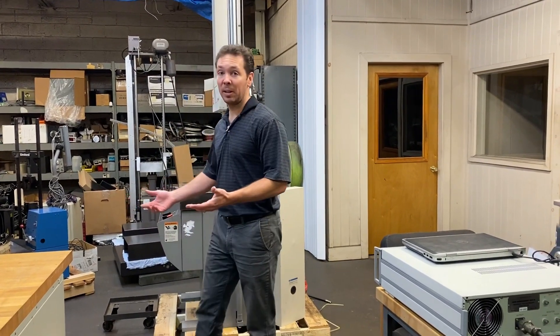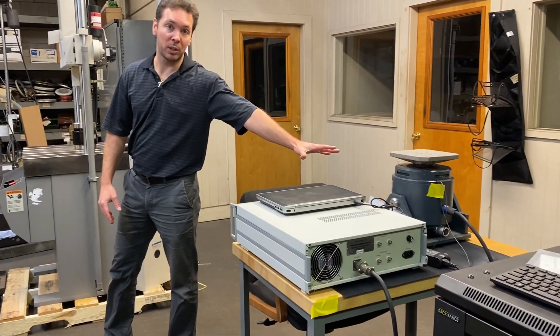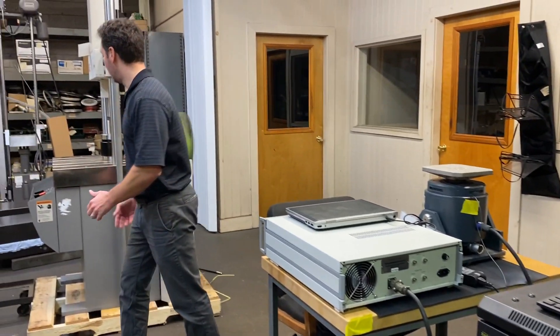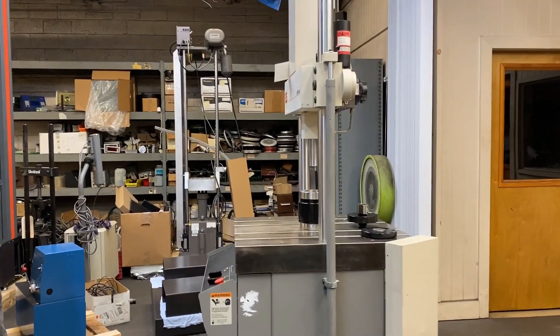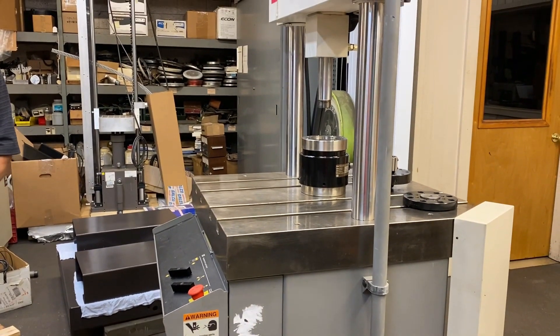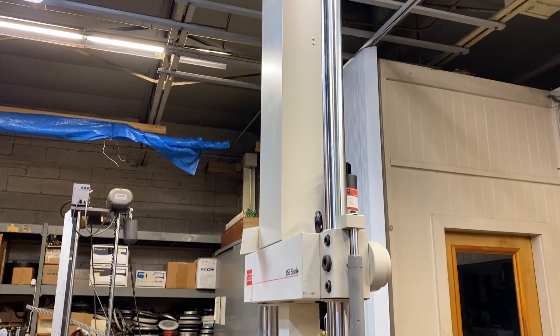Here are some of the last remaining projects in this building. We have our new mini vibration system — this is the LT50 set up with an amplifier and vibration controller. We also have this MTS 858 Bionix system with a T-slotted table that will do axial fatigue as well as torsional fatigue, either standalone or simultaneously — it's a two-channel dual-axis system.